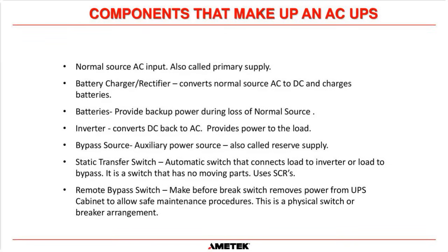Then that goes into the battery charger or rectifier, which converts that normal source AC into DC, which charges the batteries. The batteries are there to provide backup power during loss of the normal source power. And then the inverter converts the DC back to AC and provides power to the load. And then we also have, and there's a little bit of confusion about this, what's called the bypass source. It can be called the bypass, the auxiliary power source, or even the reserve supply.